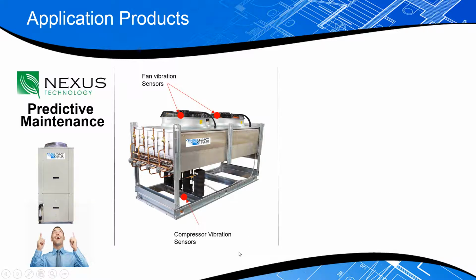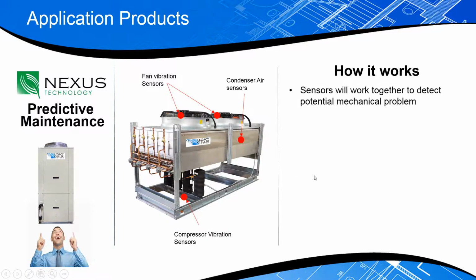The way this works is we have software—our PLC is looking for variances in critical operation of a chiller. Vibration is a very popular way to measure mechanically how a machine is doing. So we have logic in here that says, hey, if I've got an excess amount of vibration on my fans, or I've got a problem with my condenser airflow, that kind of thing.